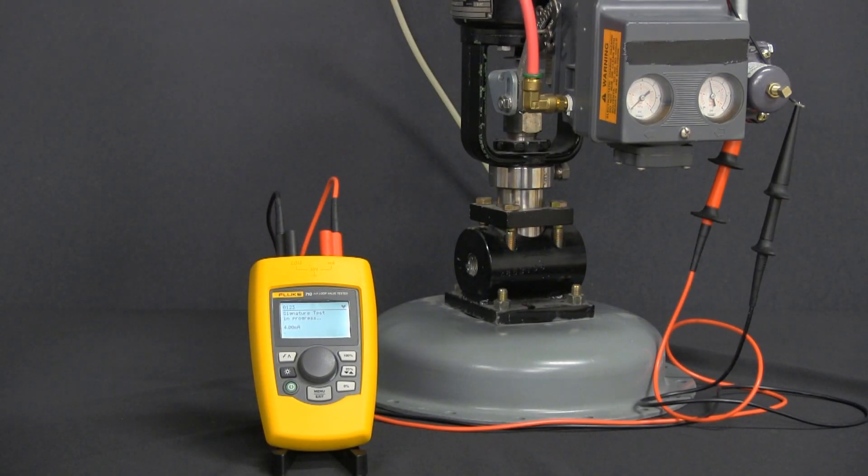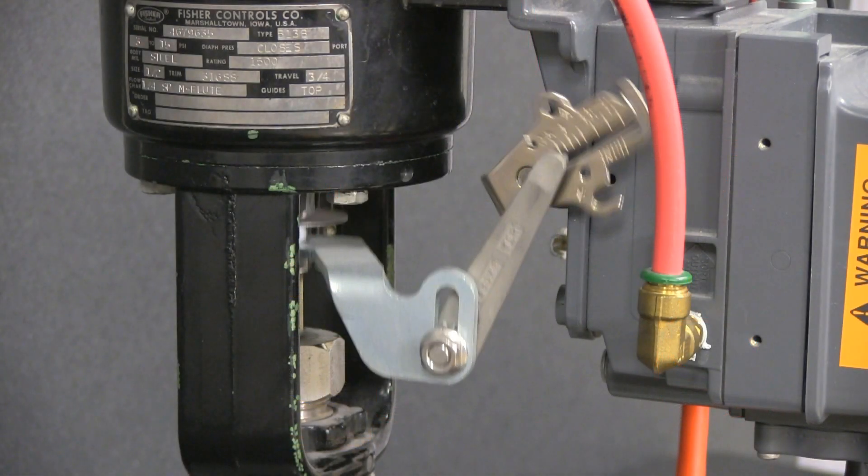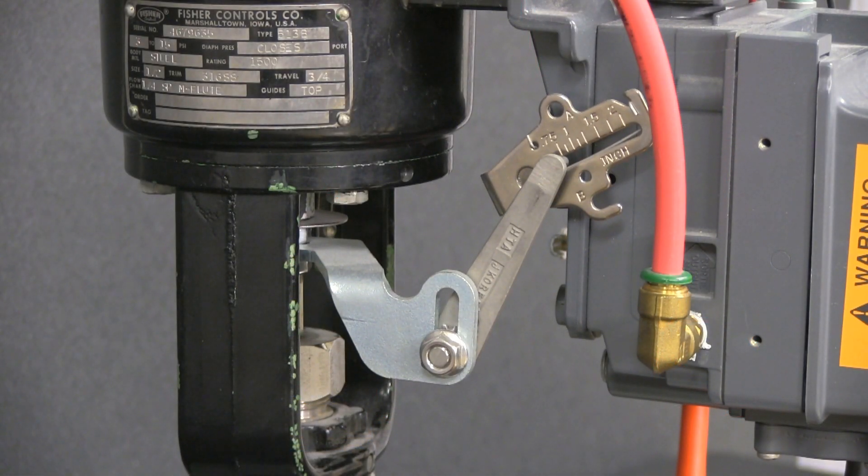So it's going to start at 3.8 milliamps and then go up to four, step by four all the way up to 20, and then it's going to come back down again.